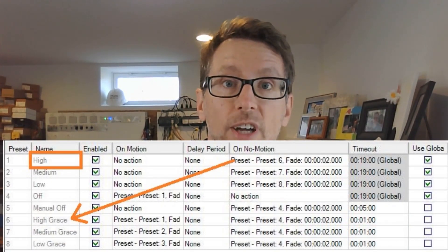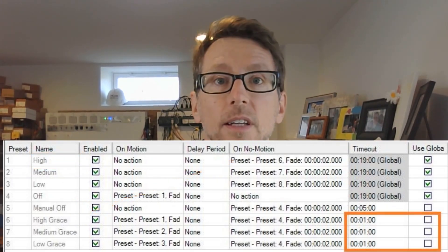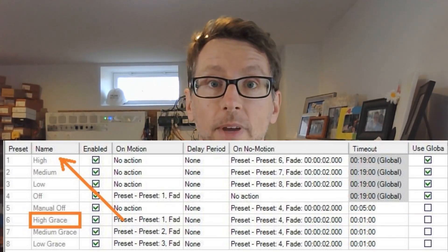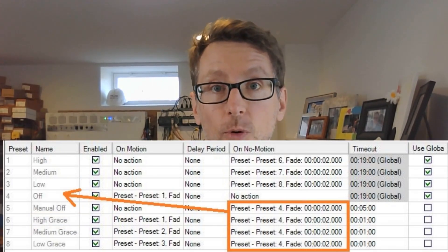Next up: grace periods. We've all been there when a sensor times out on us during a long, boring conference call — or maybe this video. To counter that, our next upgrade will be to add grace periods. This makes the lights dim down briefly before turning all the way off, to give people a warning the sensor's about to timeout. First, we add grace period presets that are dimmer than the main presets. Then, in the motion table of our sensor, we configure our main presets to timeout to our grace period presets, which have a shorter timeout than the main presets. Each grace period preset bounces back to its main preset if it sees motion, and times out to automatic off preset four if not.